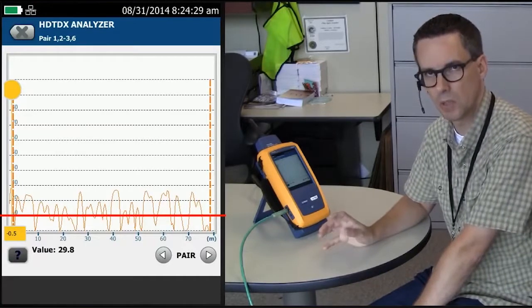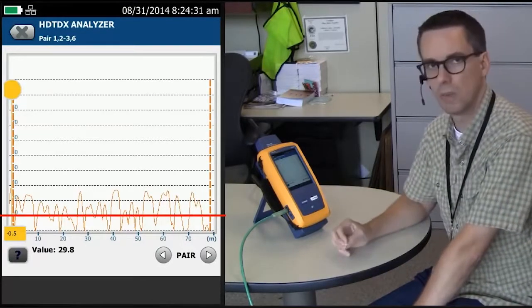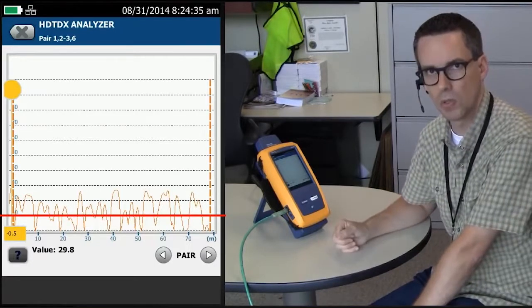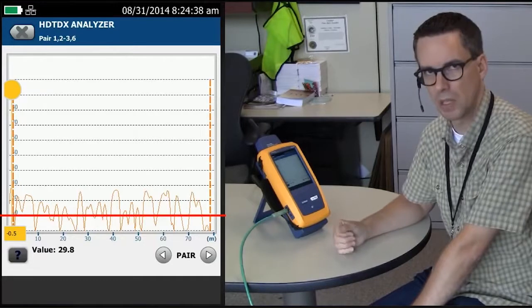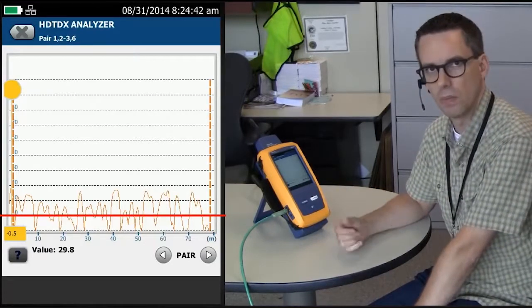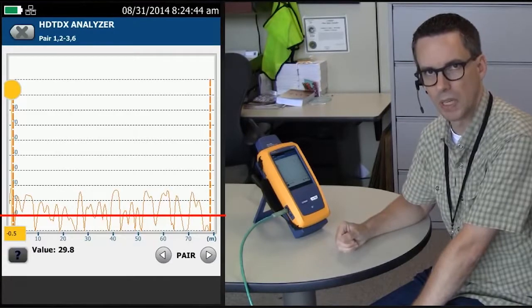Sometimes it can be a little bit subtle. But on this occasion, clearly demonstrated, we have a cable issue, the worst thing that you want. I mean, everybody's okay with re-terminating a connector. On this one, not a good situation. The cable had to be removed in order to get it to pass.